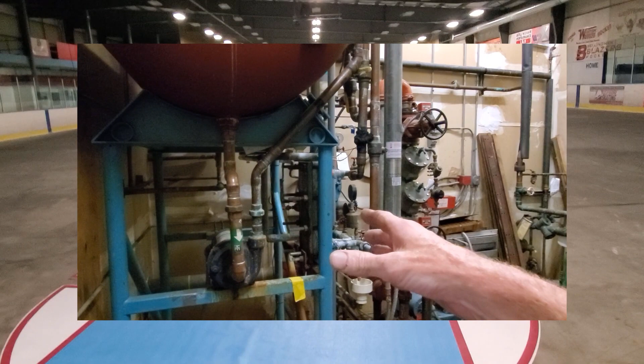And when fresh water enters the system, it's cooler, and it's cooling off the gas before it goes out to the condenser outside. So it made a big difference. Within 30 minutes, the head temperature dropped down. Let me get my numbers here. Head temperature dropped down to 175, discharge temp to 189. Suction went down to 44, 48. That wasn't really the critical number.